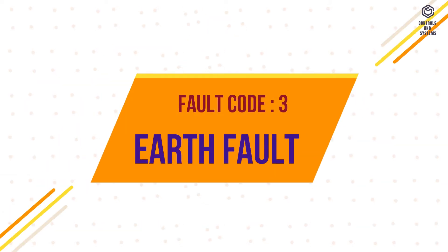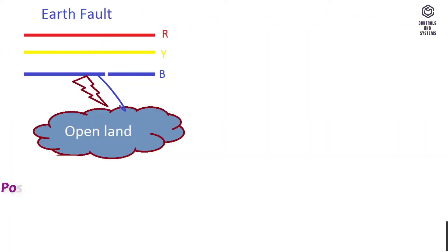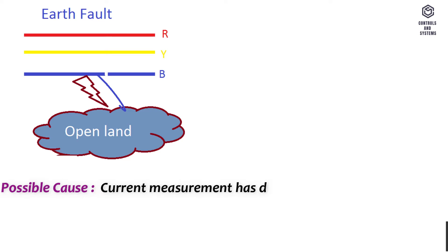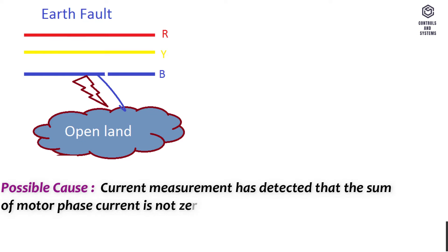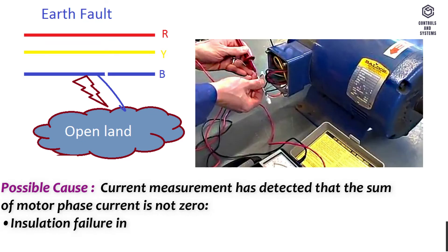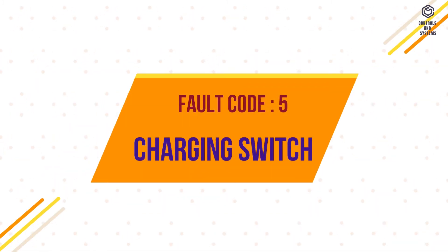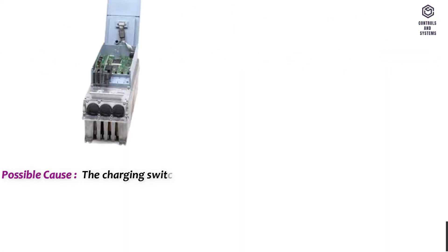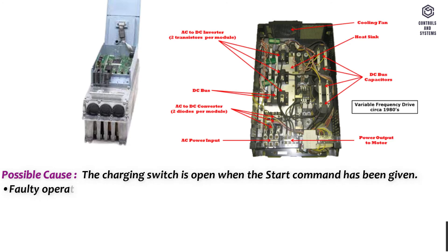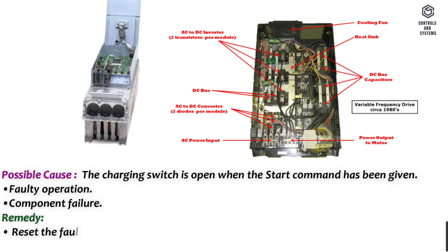Fault code 3 – Earth fault. Possible cause: current measurement has detected that the sum of motor phase currents is not zero, indicating insulation failure in cables or motor. Remedy: check motor cables and motor. Fault code 5 – Charging switch. Possible cause: the charging switch is open when the start command has been given, due to faulty operation or component failure. Remedy: reset the fault and restart.